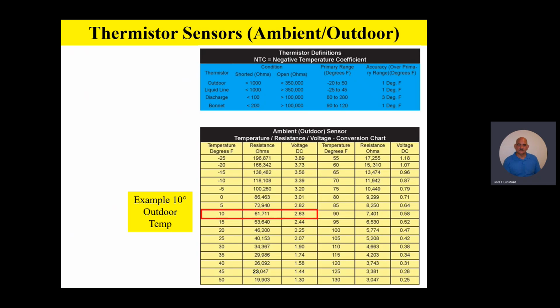Now watch this. If you take that sensor at 10-degree outdoor temperature and you plug it back onto the board, and you take your needlepoint meter leads and go in behind that sensor with it plugged onto the board in the harness itself, and you read the DC voltage on that sensor, it should read 2.63 volts DC. Let me say that one more time. If you plug the sensor back onto the board after you do your ohm check, and you take your needlepoint meter leads and dig into the back of the sensor harness, and you read the voltage of the sensor with it plugged back onto the board, it should be 2.63 volts DC at 10 degrees outside.